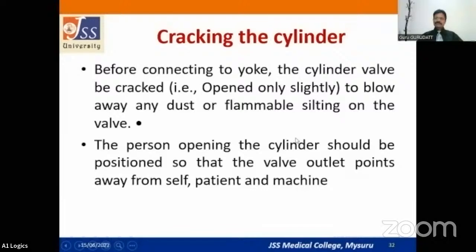Another thing commonly asked in the exam is, what do you mean by cracking of the cylinder? Before actually connecting the cylinder onto the workstation, you have to open the cylinder, because during transportation there may be dust particles inside the port. They should not enter the main workstation, because they are inflammable and can catch fire. They may also block the narrow channels of the pipings of the workstation.